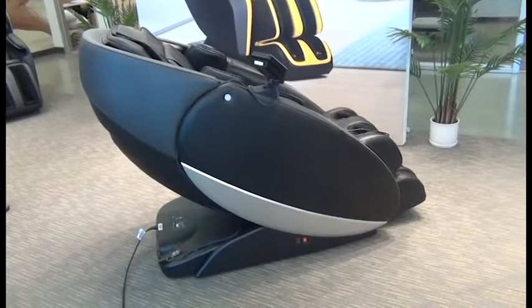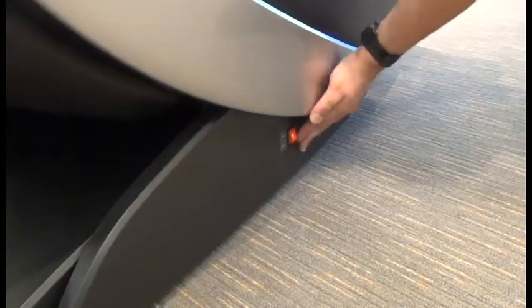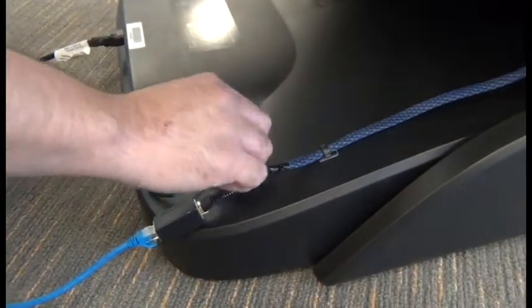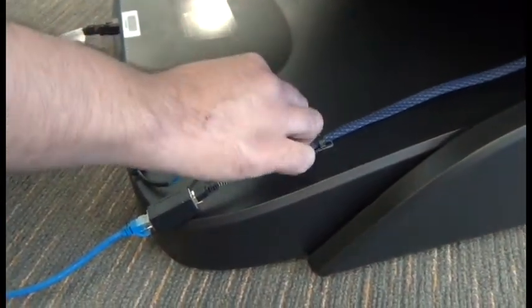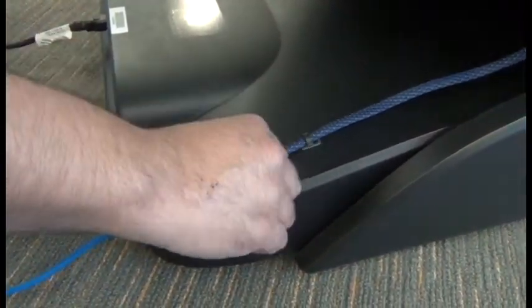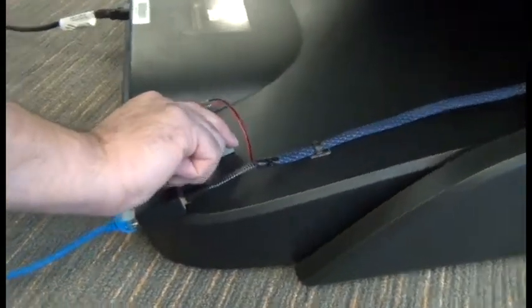To prepare to troubleshoot a Novo XT2 commercial version or Novo XT Pro connected to a kiosk system, first power off the chair, then open up the orange levers in the inline connector and disconnect the kiosk wires from the inline connector.